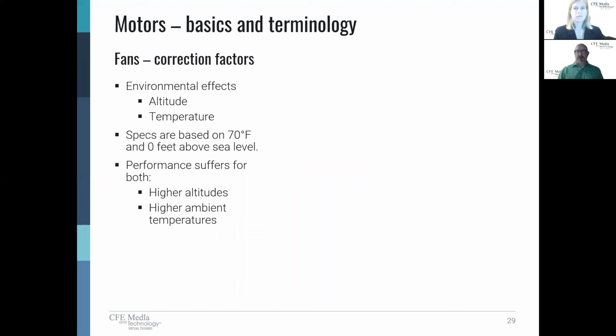Now, when we talk about air, we also care about air density. And air density is going to be affected by ambient temperature as well as altitude. So as we move up in temperature and move up in altitude, air becomes thinner. Simply put, engineers need to understand that the fans, as they're selected by the manufacturer and specified, and all their data was probably in a nice, comfortable lab. As you apply your fan, you're going to generate a difference in the environment. And that difference in the environment means you have to make adjustments. You can't just pick a fan that was sized in a lab and say, this is going to work great in my application. You have to make adjustments based on the actual environment and the system effects.